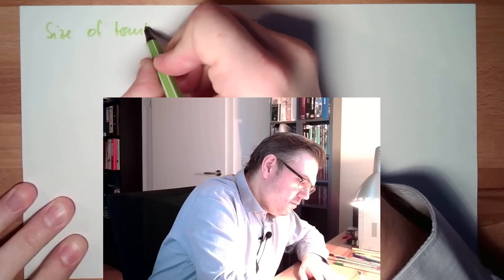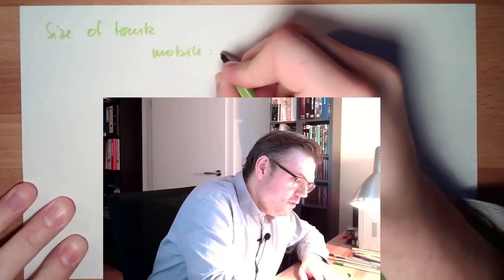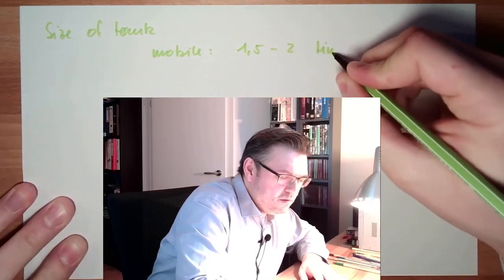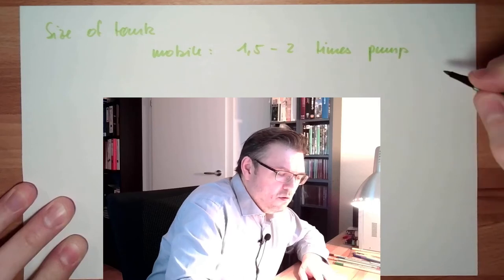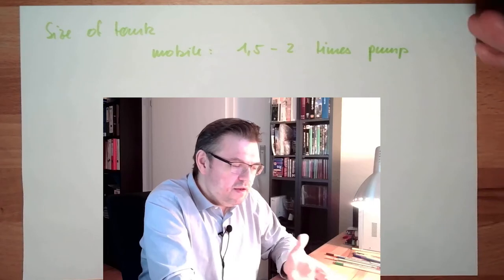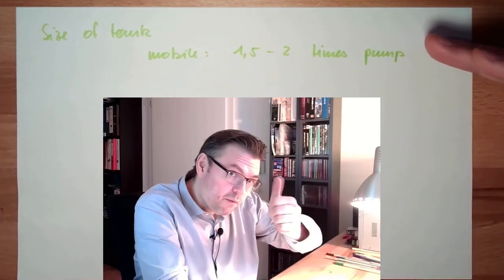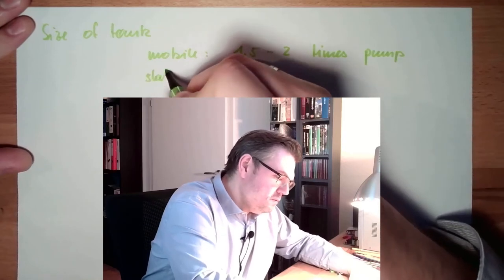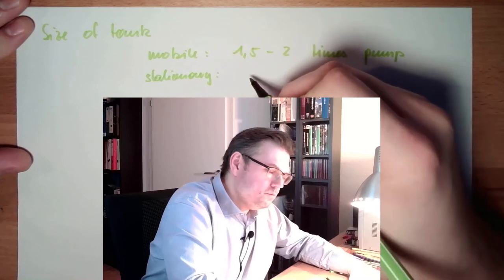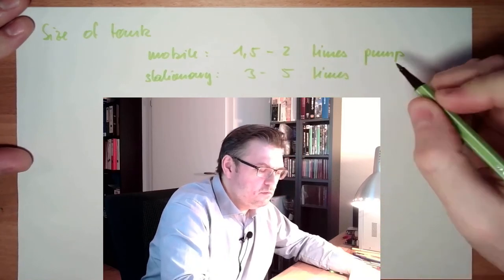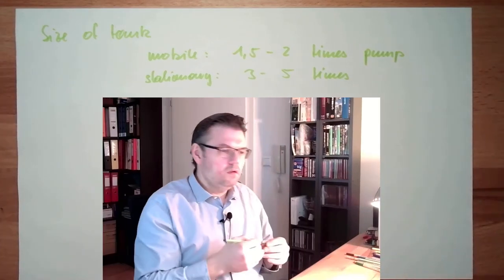There are rules of thumb. In mobile hydraulics, the size of tank should be 1.5 to 2 times the pump capacity. So if the pump is pumping out 10 liters per second, the mobile tank should be around 15 or 20 liters. For stationary applications, three to five times the pump flow rate.